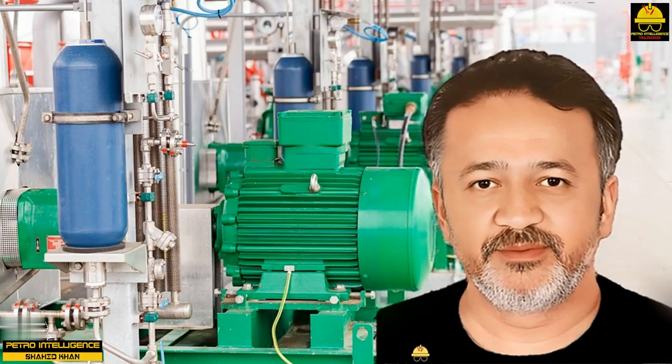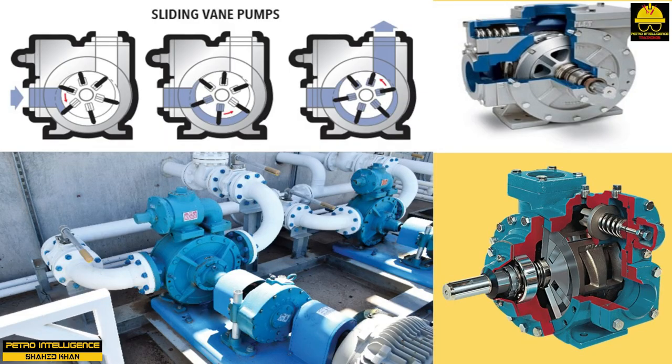Sliding vane pumps. Sliding vane pumps, as shown in the picture, consist of spring-loaded or non-spring-loaded vanes attached to a rotor, or impeller, that rotates inside an oversized circular casing. As the offset impeller rotates by the inlet port, liquid is swept into the vane slots. A small crescent-shaped cavity is formed inside the pumping chamber that the vanes extend into. As the liquid nears the discharge port, it is compressed as the clearance is narrow. The compressed liquid is released at the discharge port.